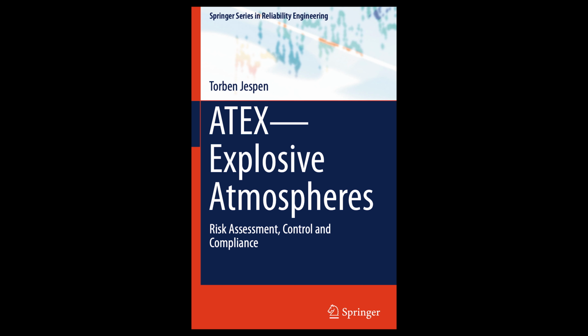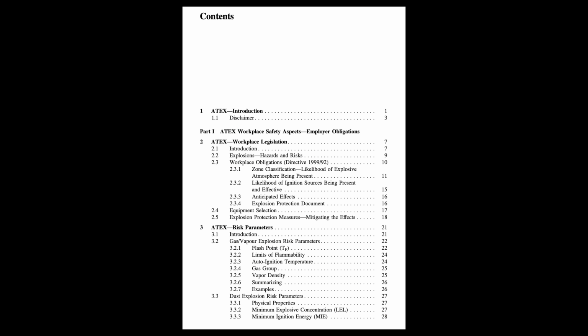Exactly. By classifying areas based on the frequency and duration that a flammable atmosphere is likely to be present, you create a framework for selecting appropriately protected equipment that won't become an ignition source in that specific environment. Okay. And the guide outlines the different zone definitions again for gases, vapors, mists, and for dusts. Can you quickly recap those?